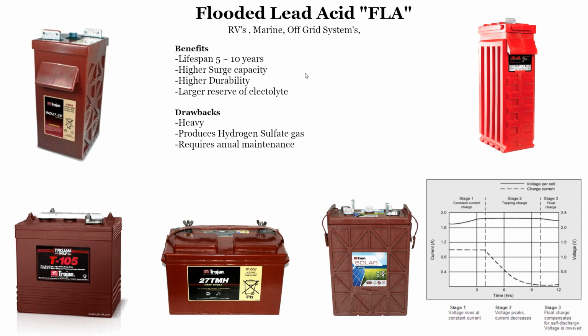Lifespan is 5 to 10 years. I say up to 10 years because I've seen these last when taken care of. With flooded lead acid batteries, and most lead acid batteries really, it's charge cycles you want to watch. If you never run these guys harder than a 50% duty cycle, you'll get much more life, usually twice the rated life. If you run them light, say at 20 or 30%, that increases the life even more. Every time you run your battery dead, that greatly reduces its life because it knocks off a charge cycle it's capable of doing.